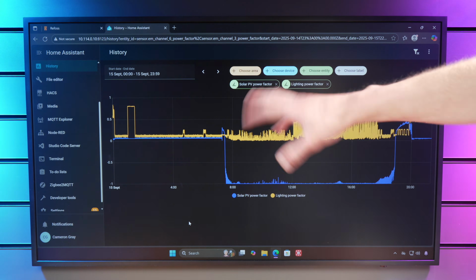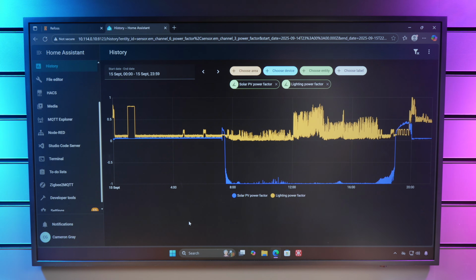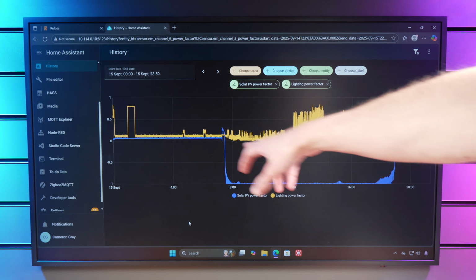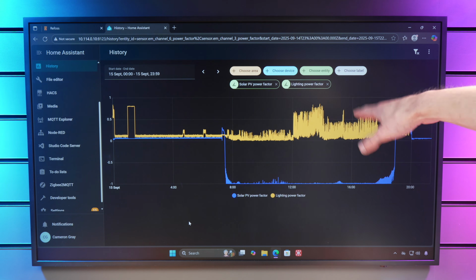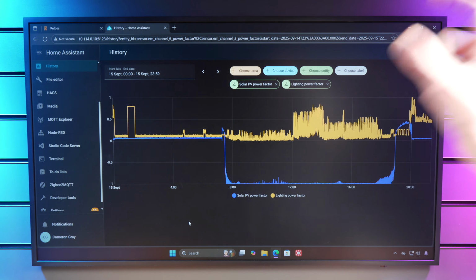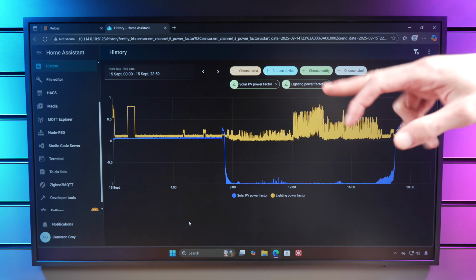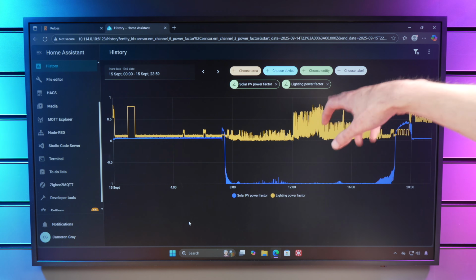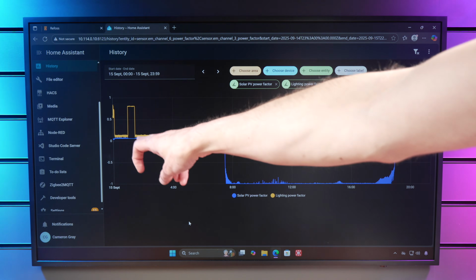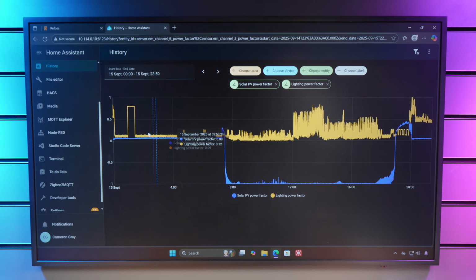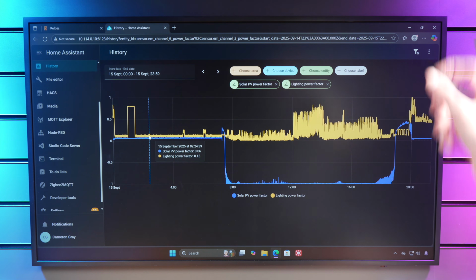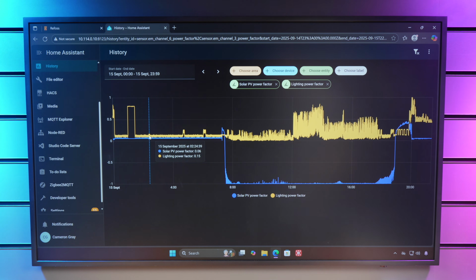Here's another example, and this is really what showed me that the power factor of different circuits on the same 2 channels was causing the issue. In blue, we have the power factor of my solar circuit, and in orange, we have the power factor of my lighting circuit. Once again, these are both on the same lettered inputs on the device. I think the solar is on C2 and the lighting circuit is on C1. Overnight, when the solar is not generating, the power factor on the lighting circuit is really stable, because the lighting circuit's power factor is normally very low, close to 0, as there's basically no lights on. And if there is, it'll be like the standby power draw through an extractor fan's timer or something like that, which would have a very low power factor.